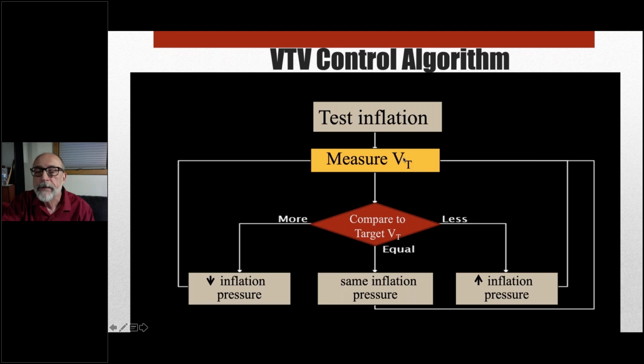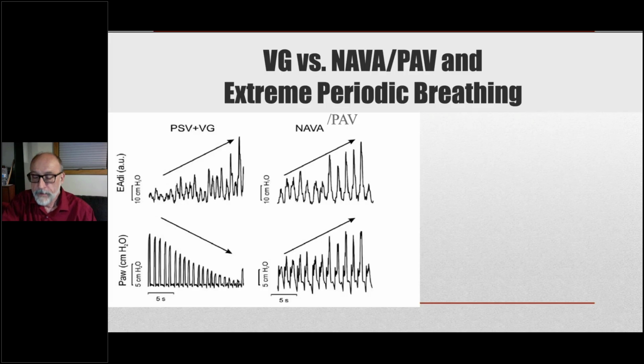The tidal volume is measured. It's compared to the target. And depending on whether the measured tidal volume is less than target, equal to the target, or above the target, the inflation pressure for the subsequent ventilator cycle is increased, kept the same, or actually decreased. And so that's a fairly straightforward algorithm. It does not make large adjustments from one inflation to the next, but it gets the job done very nicely, and there's been lots of evidence for that.